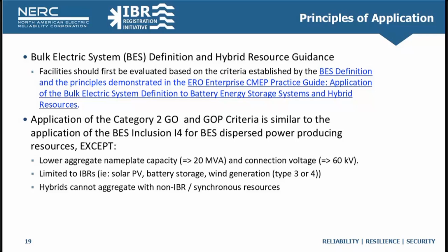This application is very similar to applying the BES definition inclusion I-4 for dispersed power producing resources, with a few exceptions. With the Category 2 criteria, we have a lower aggregate nameplate capacity threshold of greater than or equal to 20 MVA and a lower connection voltage threshold of greater than or equal to 60 kV. Category 2 criteria is limited to IBRs, where I-4 dispersed power producing resources can include, but is not limited to, solar, geothermal, energy storage, flywheels, wind, microturbines, and fuel cells. In all honesty, any further technology developed from a generation resource perspective could potentially be captured under I-4.